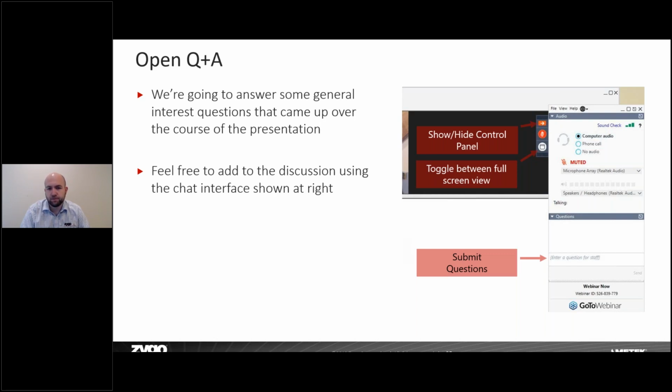Yeah, we got some good questions here. The first one that's coming in is, what is the smoothest surface you can measure using this technique? The smoothest surface that you can measure is going to be heavily dependent on your environment. To get down to the sub-angstrom type measurements, you're really going to be limited by how much noise you have and how much you can eliminate. The more sources of noise that you can eliminate, the lower you're going to be able to go from a roughness standpoint. So even though we're at 0.6 angstroms, you could go below that with a significantly better environment.